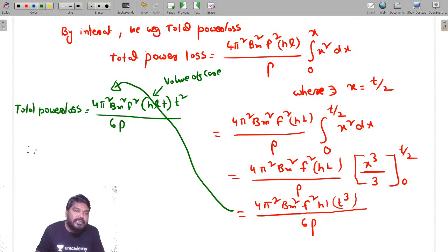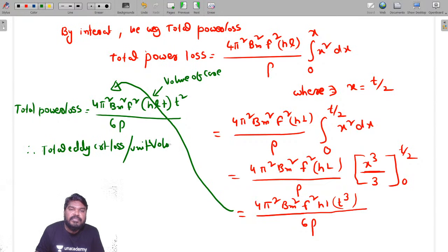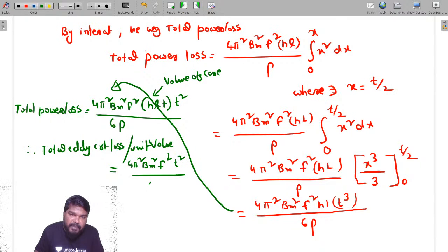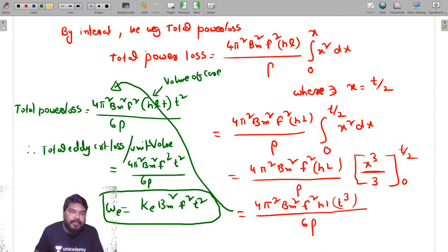Therefore the total eddy current loss per unit volume is equal to 4 pi square B maximum square f square, h l t is the unit volume, f square and t square divided by 6 rho. So we can write this as some constant Ke, giving B maximum square f square t square. This is the eddy current loss.